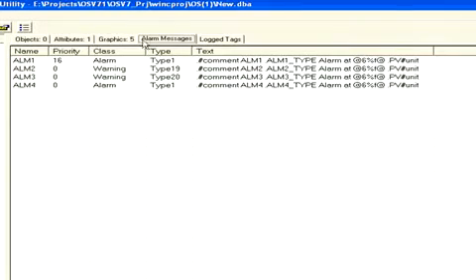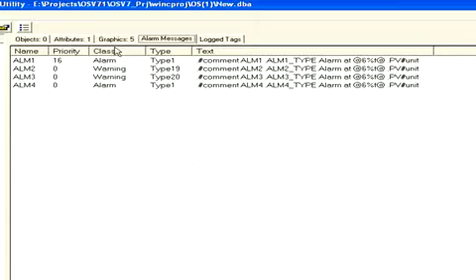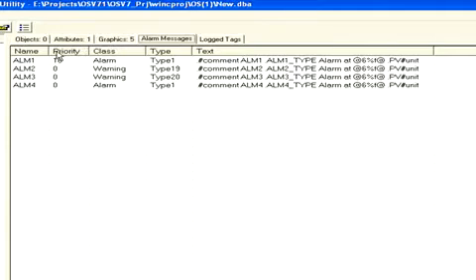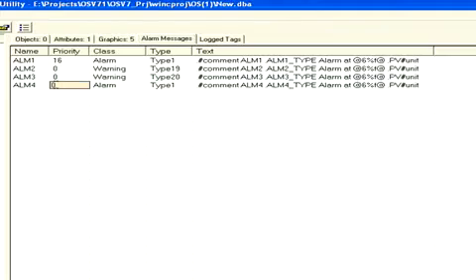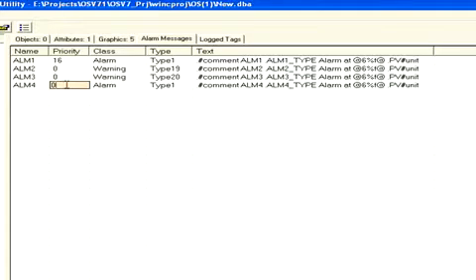The alarm tab allows you to set the alarm priority for each alarm. This information does not exist in the APACS alarm block, but is very helpful in managing system alarms. Notice that alarm 1 priority is already set to 16. I'm going to change the priority for alarm 4 to 4.